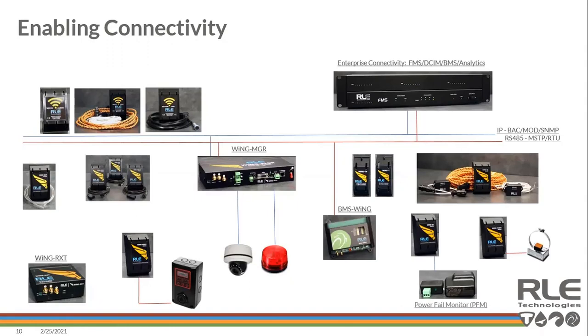If you notice, it's only connected to the red link, so BACnet or Modbus RTU, BACnet MSTP are the only ways you're going to be able to get that to communicate. A lot of IT folks prefer this model just because it does not have any way to touch an IP network. But if you look at the Wing Manager again on the left, you'd also see that, with all the web user interface -- and we'll go through some of that shortly -- all of the setup becomes streamlined and easy with all the other bells and whistles.